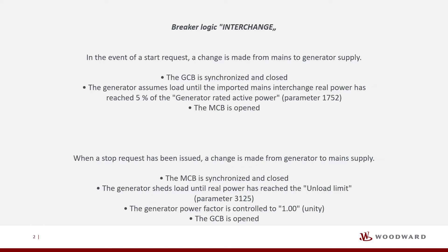The engine is shut down following the configured cool-down period. Breaker logic interchange: in the event of a start request, a change is made from mains to generator supply. The GCB is synchronized and closed. The generator assumes load until the imported mains interchange real power has reached 5% of the generator rated active power, parameter 1752. The MCB is opened. When a stop request has been issued, a change is made from generator to mains supply. The MCB is synchronized and closed. The generator sheds load until real power has reached the unload limit, parameter 3125. The generator power factor is controlled to 1.00 unity. The GCB is opened.